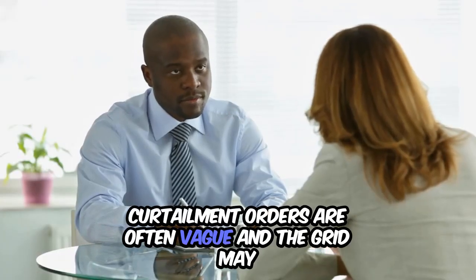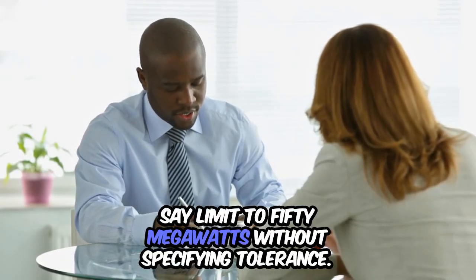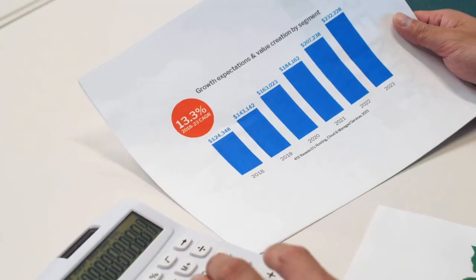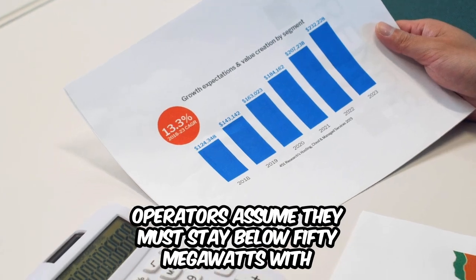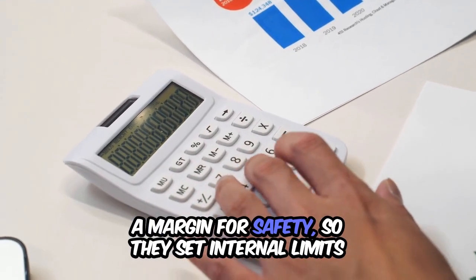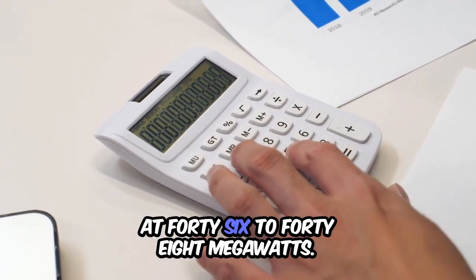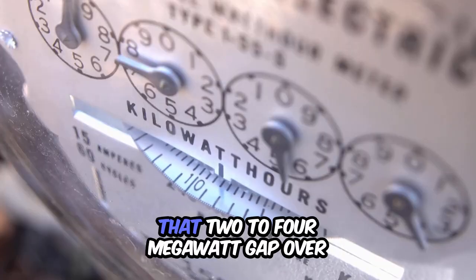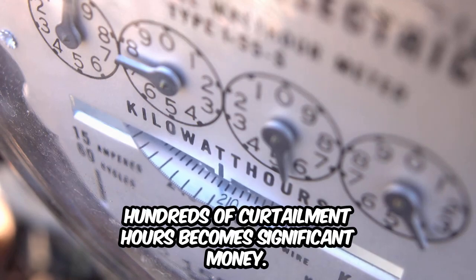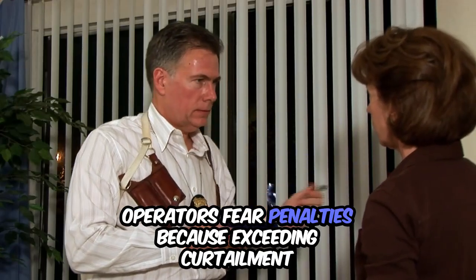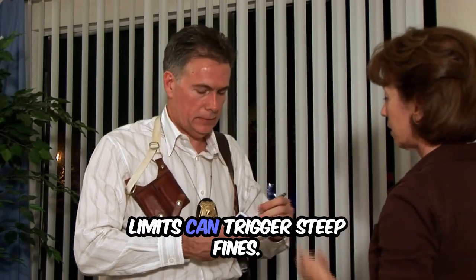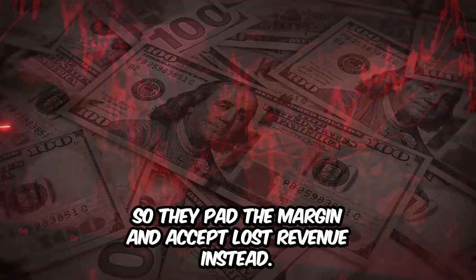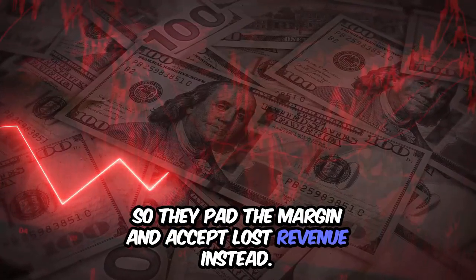Curtailment orders are often vague, and the grid may say limit to 50 megawatts without specifying tolerance. Operators assume they must stay below 50 megawatts with a margin for safety, so they set internal limits at 46 to 48 megawatts. That 2 to 4 megawatt gap over hundreds of curtailment hours becomes significant money. Operators fear penalties because exceeding curtailment limits can trigger steep fines. So they pad the margin and accept lost revenue instead.